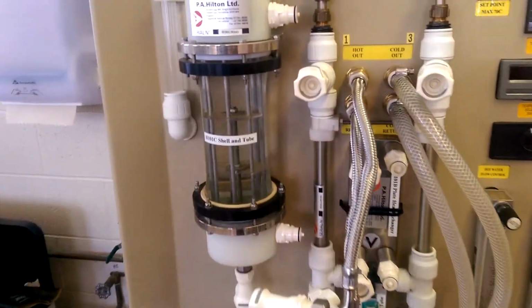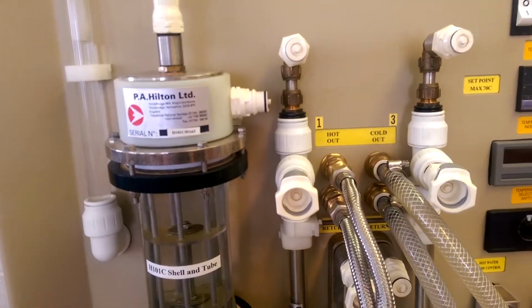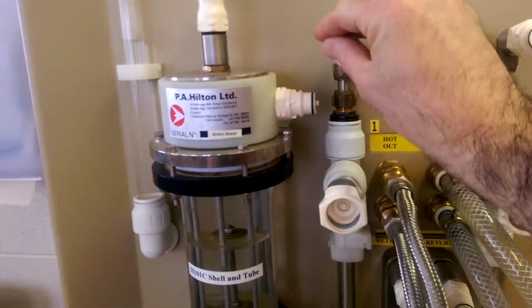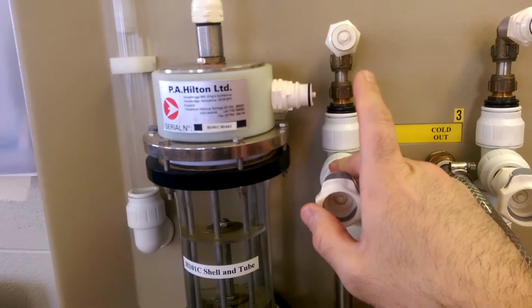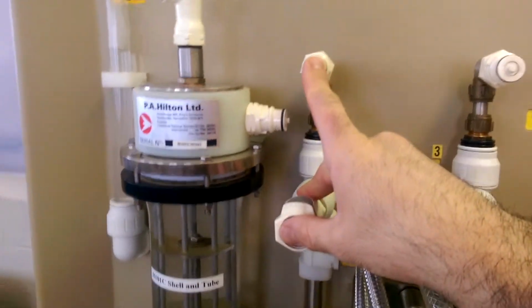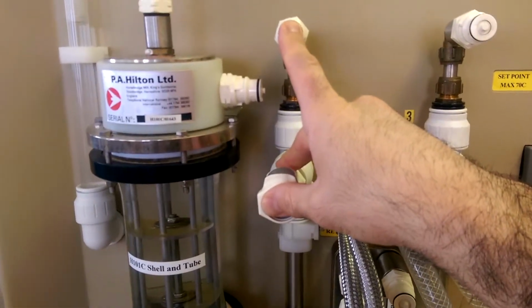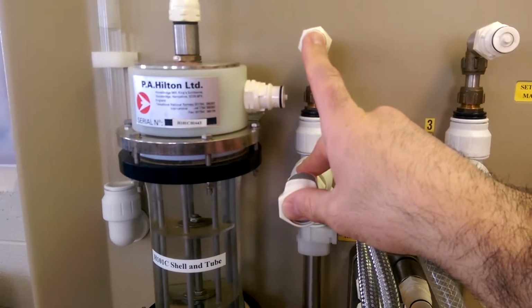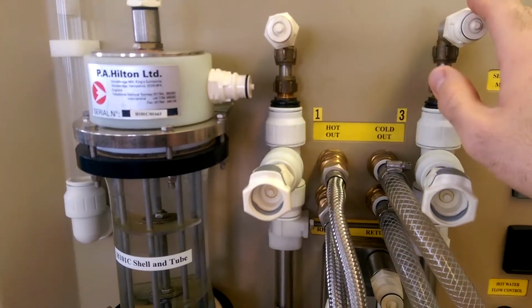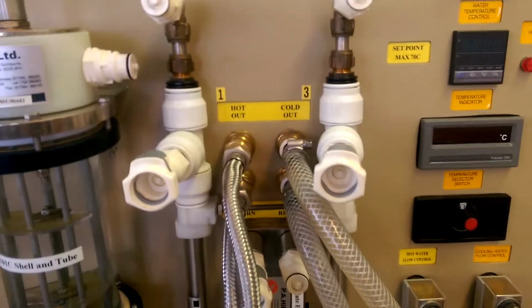The other thing is that you can arrange each heat exchanger to be parallel or counterflow. Parallel flow is done such that the hot water and the cold water go into the heat exchanger on the same side. That would be parallel flow. If you have the hot water coming in on a different side of the heat exchanger than the cold water, then that would be counterflow.